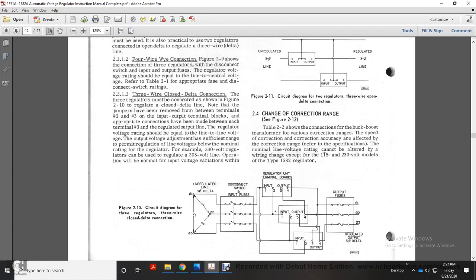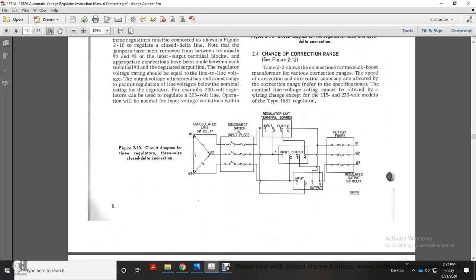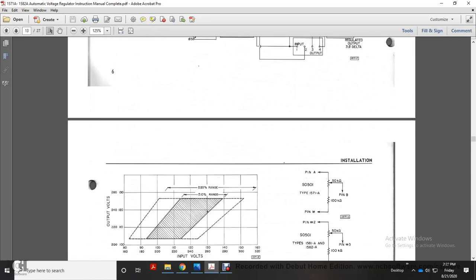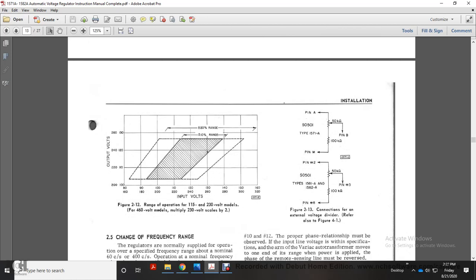2.4 Change of Correction Range. Table 2.2 shows the connections for the buck boost transformer for various correction ranges. The speed of correction and correction accuracy are affected by the correction range. Refer to specifications. Nominal line voltage rating cannot be altered by wire changing, except for the 115/230 volt models of the type 1582 regulator. Figure 2.10 shows the circuit diagram of the 3 regulators, wire closed delta: the unregulated 3-wire delta, disconnect, input fuses, regulated terminal board 1, 2, and 3 with inputs and outputs, output fuses, and the regulator output 3 delta. Figure 2.12 shows the rating of the operation of the 115/230 volt models, the output voltage over the input voltage. And Figure 2.13 connects to the external voltage divider. Refer also to Figure 4.1, which shows pin A, pin B, pin M, pin 2, pin 3, pin 8.